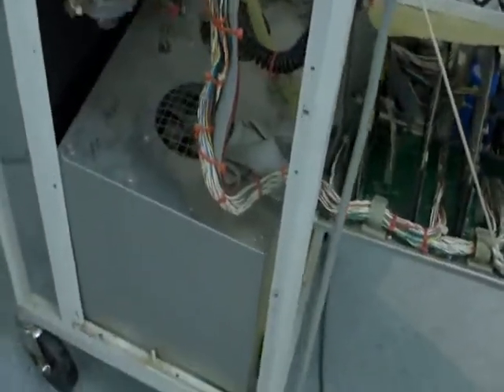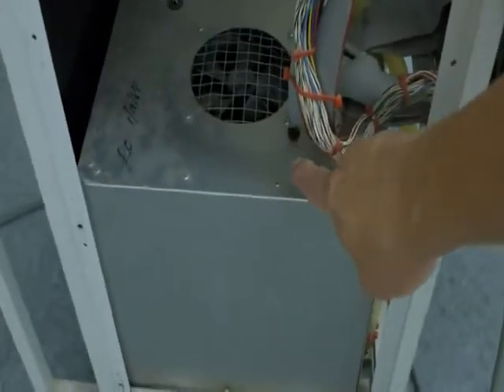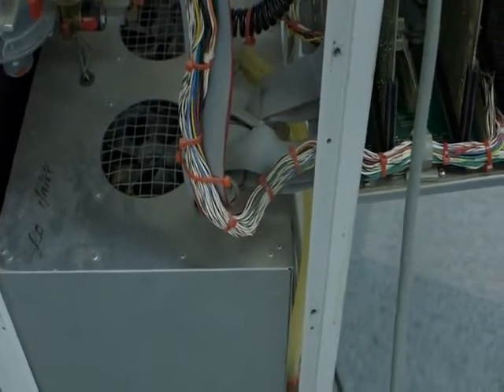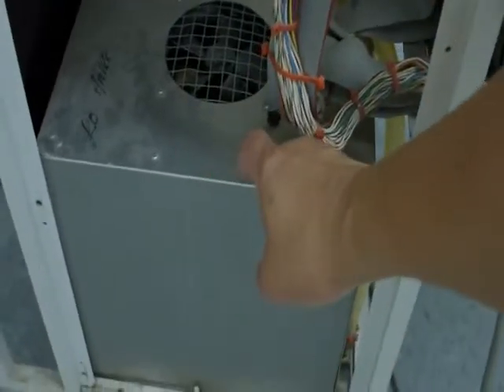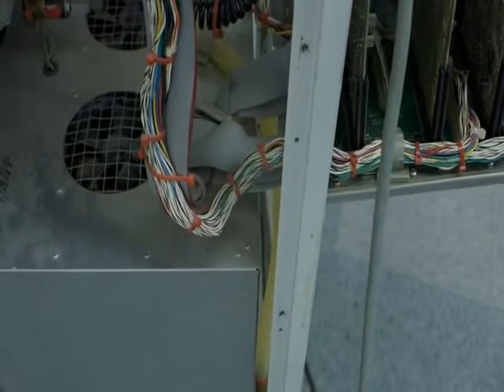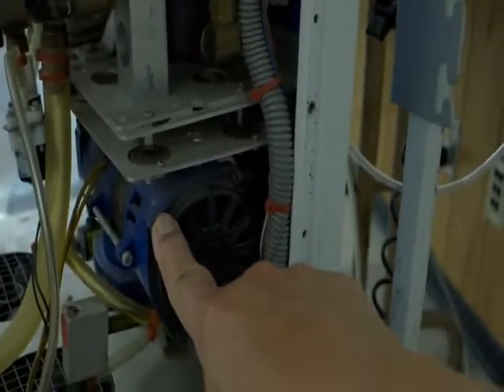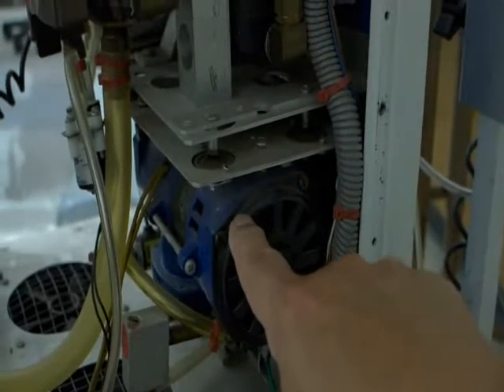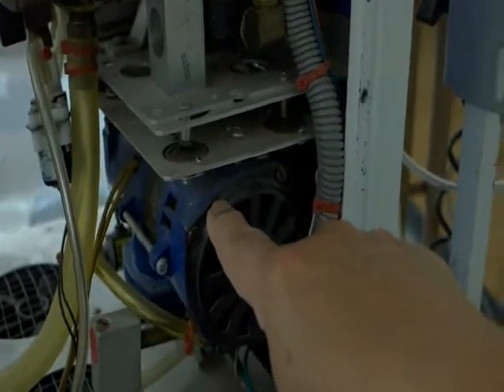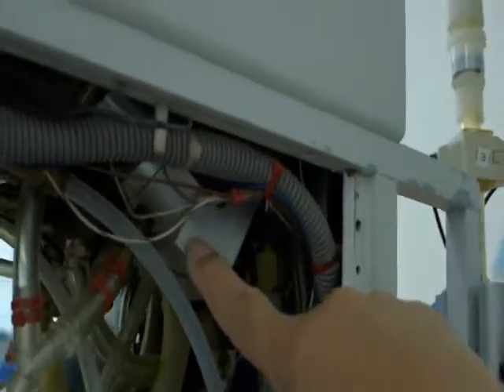Underneath the machine, down below, you're going to see that we have an internal air compressor. Okay, so in case we lose the oxygen or air from the hospital, we can run on the air compressor only. It has a built-in air compressor down here. And also a whole bunch of the pneumatic system. It's got pressure regulators and a demand valve system. Also over here, this is the pump that functions as the driving force for the nebulizer.